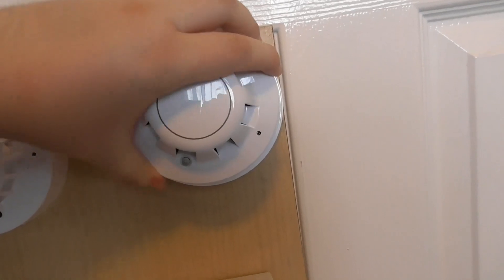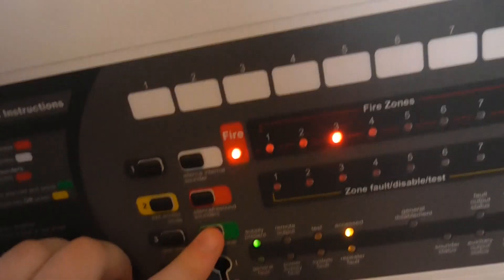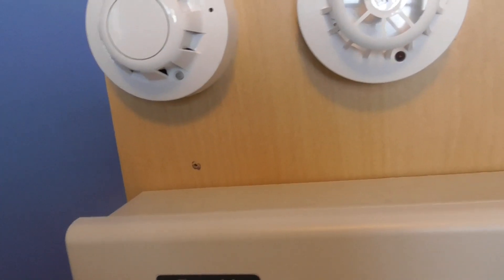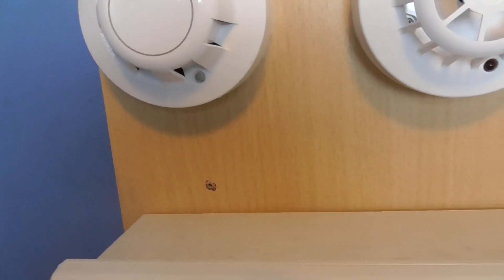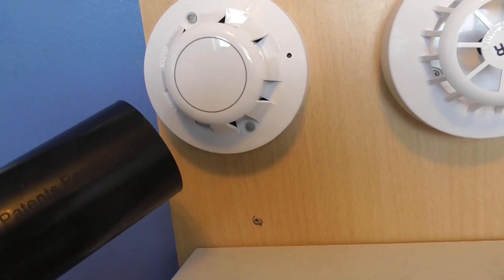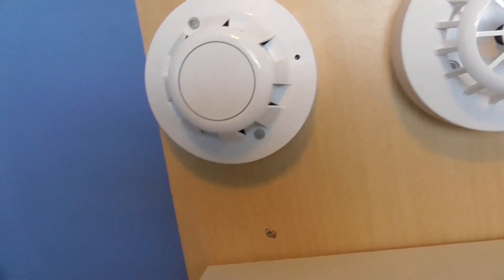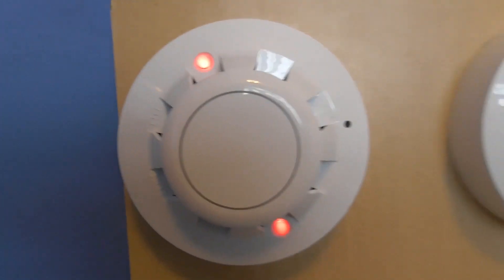I'm going to take off the head, blow into it, put it back up, and then reset. Then let's test the optical on zone one, and then we'll test the call point to finish the test. This might be a very quick test today.